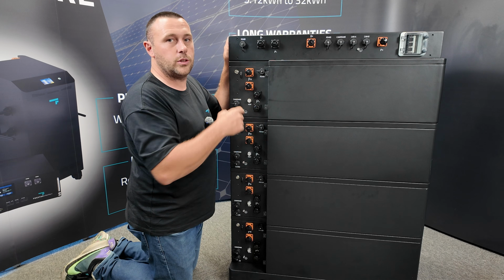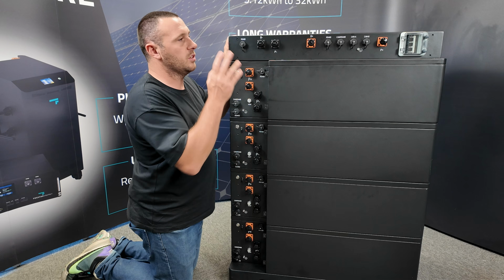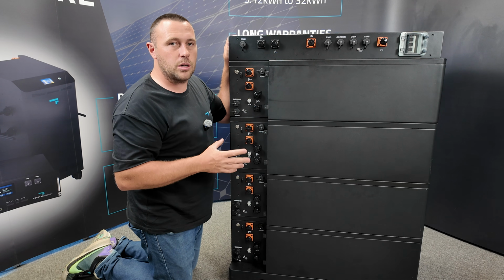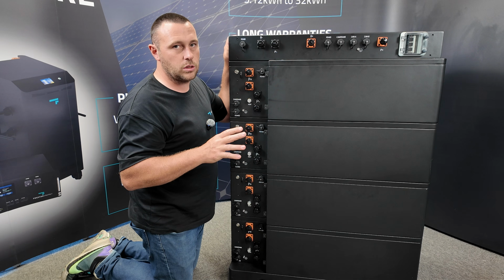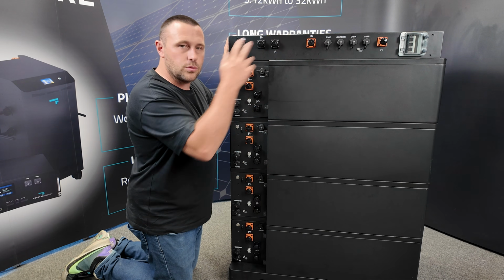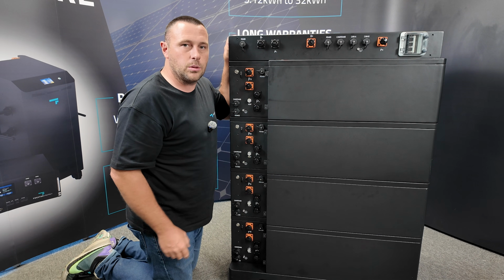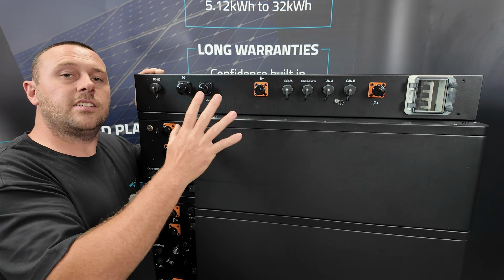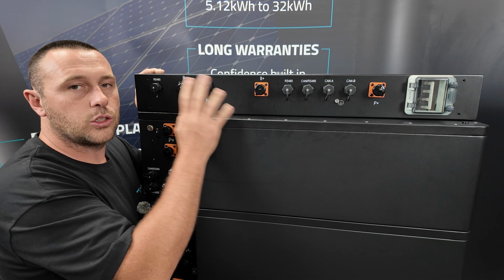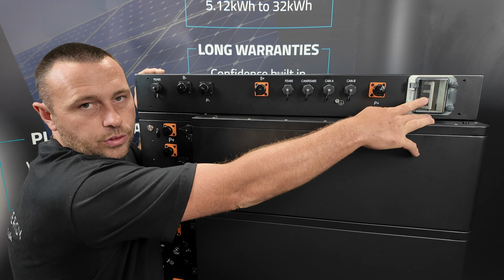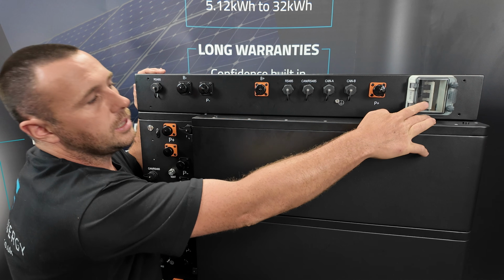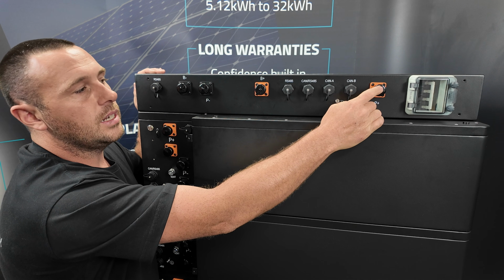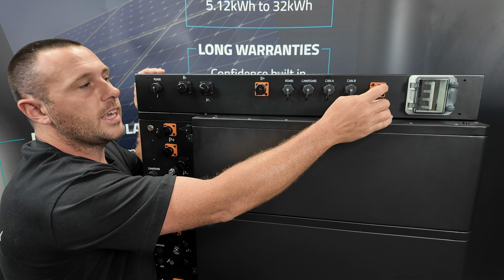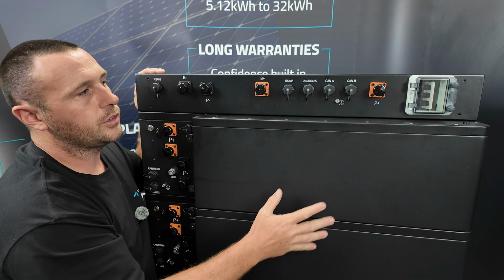Now that all the covers are off, you can see all of the ports on the modules and the control panel. This can look a bit daunting, but don't worry, it's not too bad. Let me break it down for you. Let me show you exactly what's going on and what goes where. Okay, so starting at the top of the battery with the control panel. Here we have our 375 amp breaker. There is the positive lead out to your inverter. So this is the output from the whole of the stack battery.